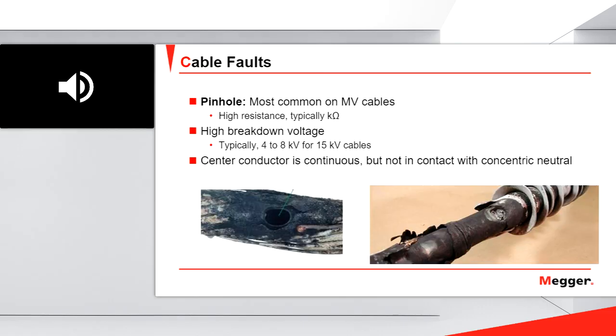Talking of typical faults, or the most common faults in medium voltage cables, I would say that maybe the most common fault is the pinhole fault. It's a high resistance fault. For instance, for 15 kV cables, the breakdown voltage for a pinhole fault will be between 4 and 8 kV. We have continuity between the conductor and the concentric, but at some point in the cable we have a perforation, a hole in the insulation. So this is a very, very common fault in medium voltage cables.